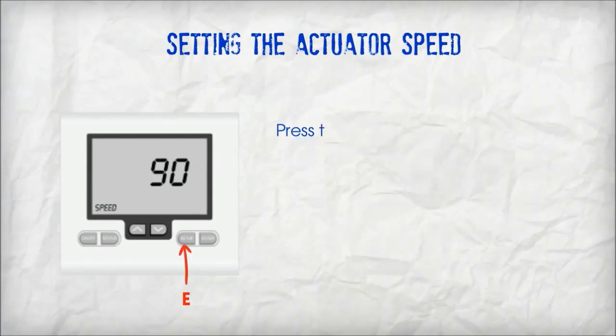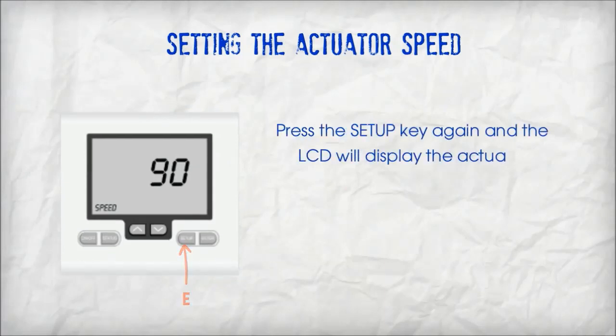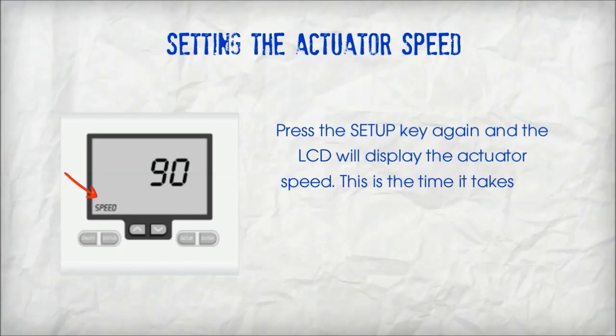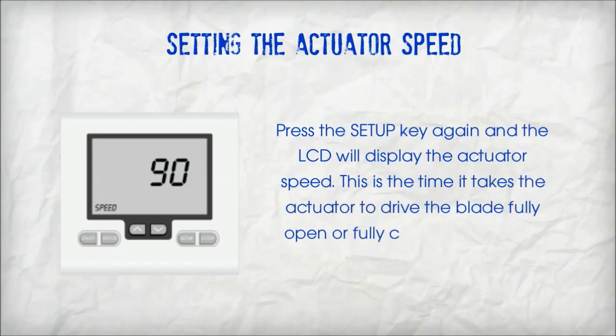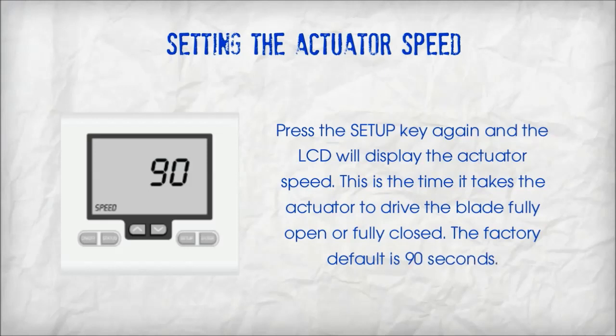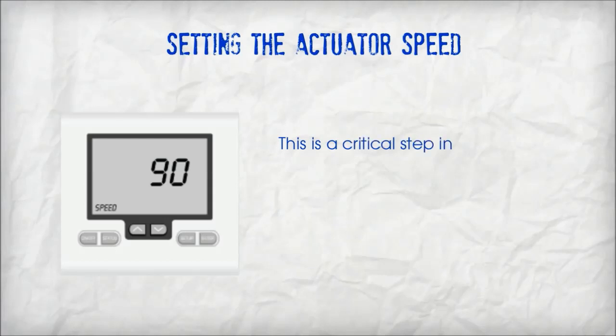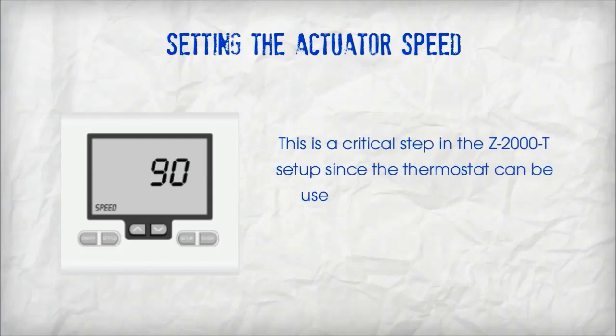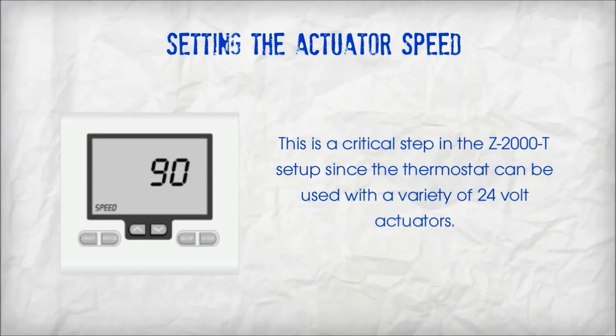Setting the actuator speed. Press the setup key again and the LCD will display the actuator speed. This is the time it takes the actuator to drive the blade fully open or fully closed. The factory default is 90 seconds. This is a critical step in the Z2000T setup since the thermostat can be used with a variety of 24-volt actuators.